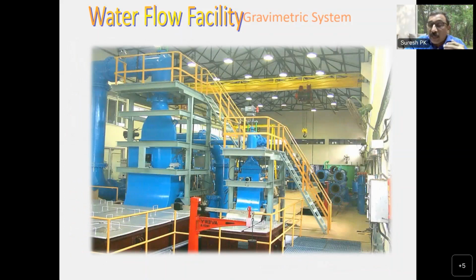That is, you have a flow meter which is to be calibrated from 50 to 100 meter cube per hour, or say 10 to 100 meter cube per hour. You do the calibration at 10, you do the calibration at 20, 30, 40 at different equal intervals, and you concentrate more on the flow rate at which the flow meter is being used maximum, so that you can minimize the error at that point and make the flow meter more effective, more accurate during its course of service in the industry. So this is the water flow laboratory which uses a gravimetric flow system.